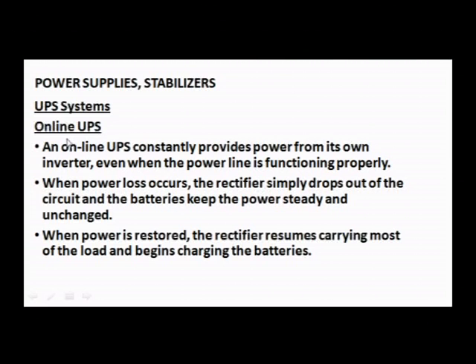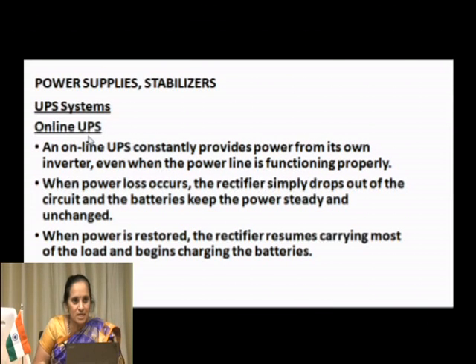Finally, coming to the online UPS, the most preferred type - it constantly provides power from its own inverter even when the power line is functioning properly. Continuously it keeps the battery in line, and when power loss occurs, the rectifier simply drops out of the circuit and the batteries keep the power steady and unchanged. When power is restored, the rectifier resumes carrying most of the load and begins charging the battery again.